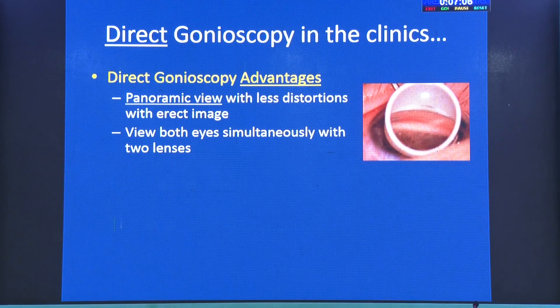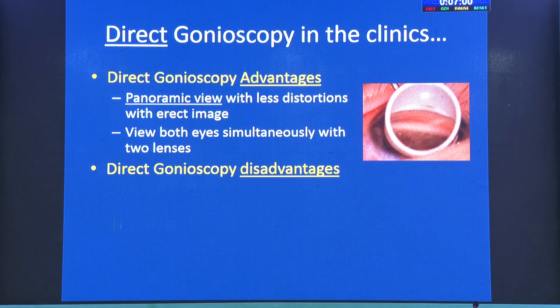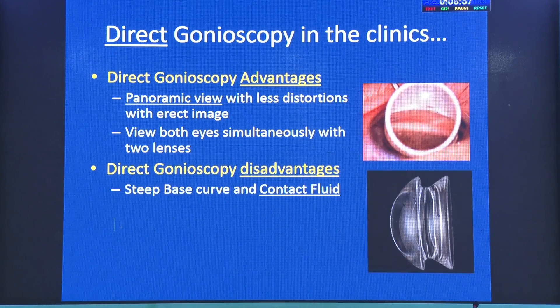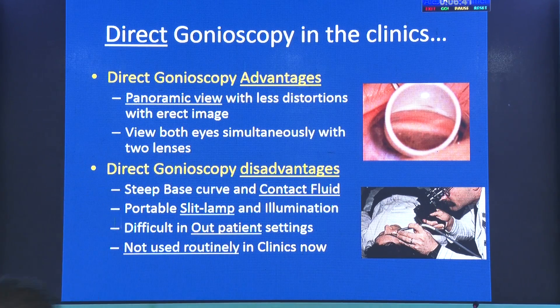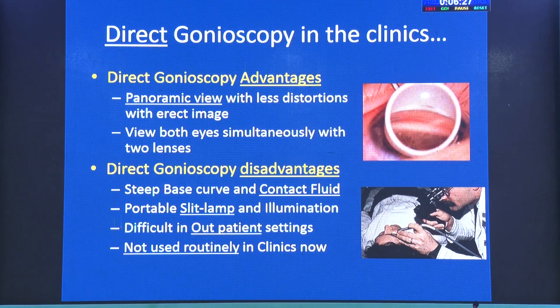These are the common ones; you can visualize with both eyes. Initially in outpatient settings, gonioscopy was done in a different way — it had a steep base curve requiring contact fluid, and the slit lamp used was very heavy, about a kilogram. A pulley with a counterweight was needed, plus a cold indirect light source. It was quite a cumbersome setup, and it is not routinely used in clinics anymore. However, we still need to develop expertise for it because it is used in the operating theater.